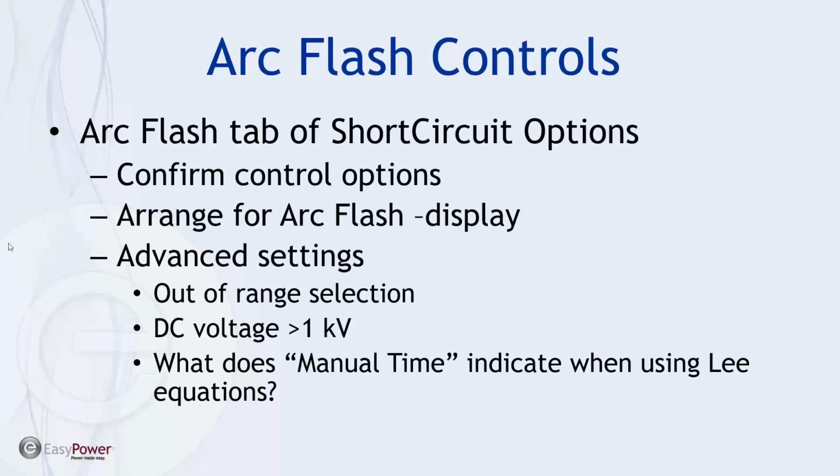And we've seen one case where manual time was indicated when the 2-second rule was being used. It also would be an indication where we're exceeding the time limit of 1,000 seconds, and it would indicate a manual time. But what does it mean when we're utilizing Ralph Lee as an alternative because we're outside the scope of the 15K limit on 1584?